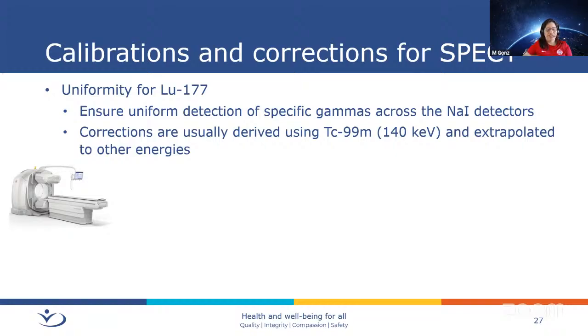For SPECT cameras, we have sodium iodide detectors, right? They're scintillators and they have PMTs and stuff like that. So we had to check that when we're using the lutetium energies, the response of the detector and the whole system is appropriate. Usually in NUCMED, because technetium-99m is the main diagnostic isotope that we use, that's what we calibrate the cameras with, because 90% of the images that we take for SPECT, well, maybe 80%, are technetium-99m. So we calibrate the equipment at 140 keV, but lutetium is not at 140.